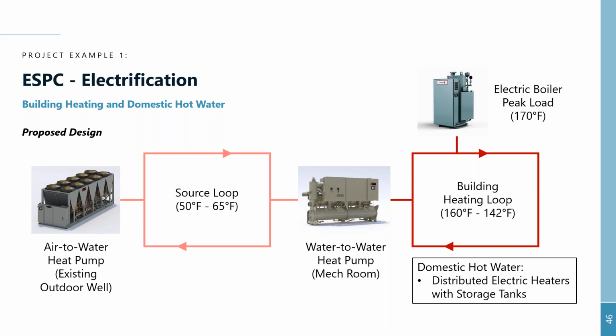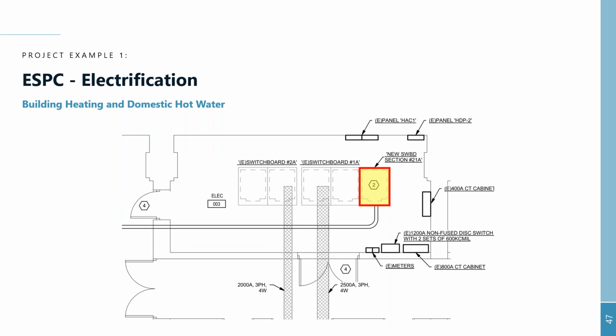The challenge with this approach was not so much the overall power to the building, that was a challenge, but I think where the power is delivered was equally as much of a challenge. And I'm going to hand it over to Kulai to dive into those details. Thank you, Teresa. So this is an existing building, with existing switchboards. They have some lifetime left in them, not much, but as you may expect, they are already full. There is no space in them for additional breakers.